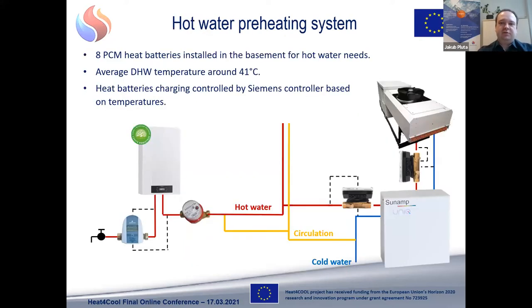In the hot water preparation system, we also have two parts of the system connected from the eight heat batteries with the phase change materials. They are installed in a room in the basement. The first part is between the heat pump and the heat batteries. This is the heat batteries charging circuit with a circulation pump, which is controlled by a separate Siemens controller, and its work is managed based on the temperatures from the sensor installed inside the heat batteries. With the system we are able to provide to the apartments hot water at a temperature of around 41 degrees. And it is enough for a day to charge the heat batteries only once to provide the hot water to the apartments.